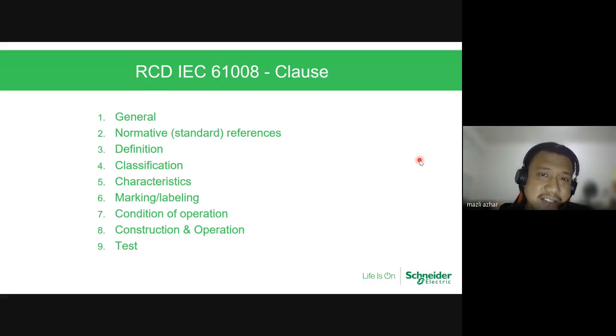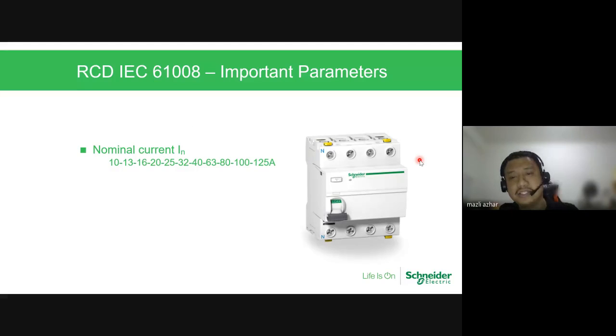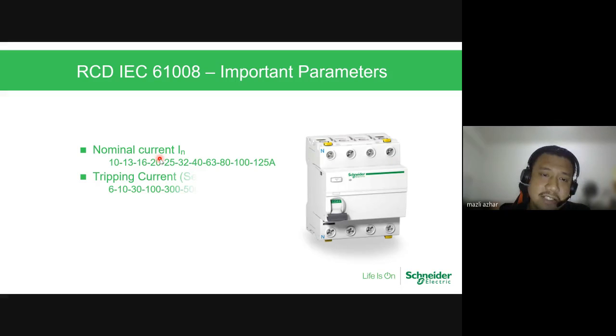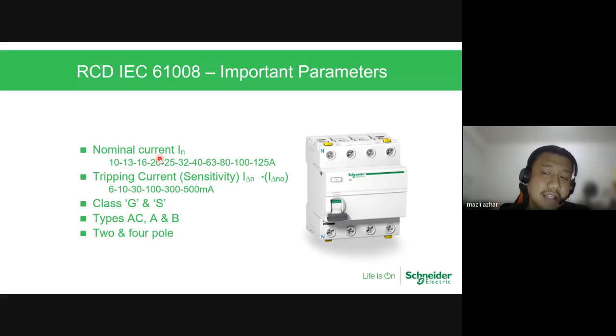So under IEC 61008, the clause, this is where I will not go deep into each one of these, but every manufacturer has to comply to ensure that the product is safe to be used, and to ensure the continuity and the performance of the products comply with the standards. So important parameters, normally you can see on a breaker, RCD. You can see the nominal current stated there. You can see the sensitivity, 6 milliamp, 10 milliamp, 30 milliamp, 100, 300, 500 milliamp. Class G and S, general and selective. Type AC, A and B. I will go in depth on what AC, A and B are. And then 2 and 4 poles.